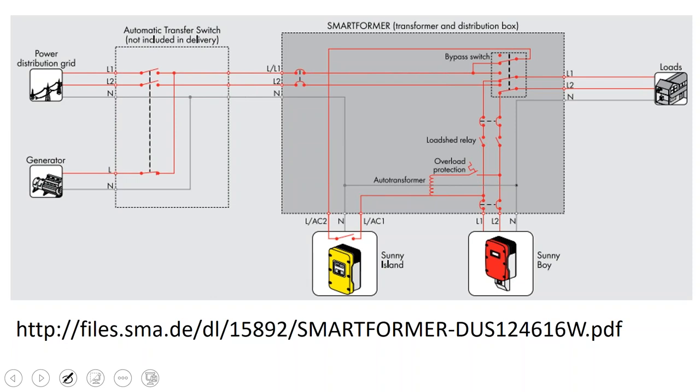In Hawaii, they have a mode called zero export mode, where the batteries are not allowed to export onto the grid, because they have too much solar being outflowed. And so they have to have the inverter be grid connected, but they also have to have the inverter dial back its production so it doesn't outflow. So there's a variety of software settings in your higher end inverters, and in particular your higher end string inverters.